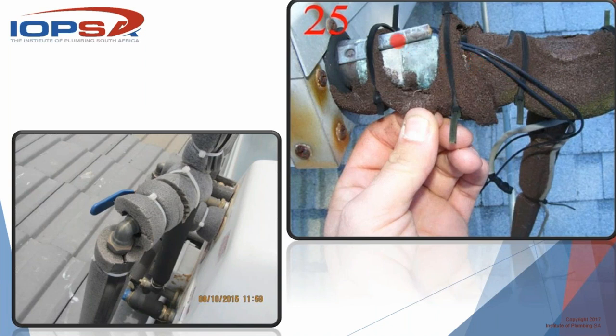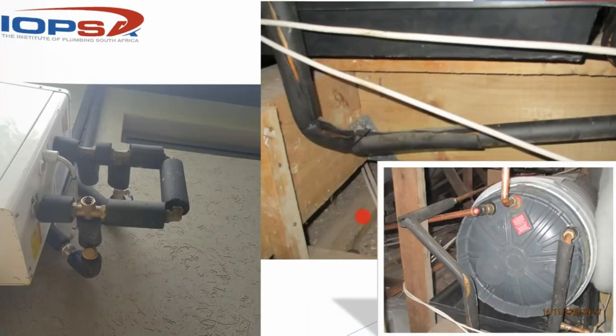Worse than that is the fact that this guy's temperature probe is now just floating around in free air, and the entire performance of the solar system is reliant on one little piece of lagging that wasn't protected and is now eaten away by the sun. And so the entire system falls flat for want of a little bit of paint. And it's these details that Mrs. Jones does not realize, and they happily live forever after on electrically heated water, and they think they're doing the planet a world of good when in fact it's just a nightmare.